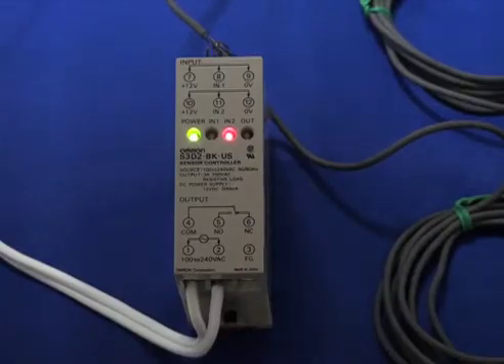Also consider that this same sensor controller can be used for the opposite application when you're trying to determine when you're running out of a product, like in a consumption type application. For instance, a gluing machine or a printing machine where you're trying to keep track of the consumption of ink or glue. In that case, you reverse your sensors, you change a dip switch, and then you have the reverse logic where as your tank becomes empty, your low level sensor tells a pump to turn on and it pumps ink into your vessel and stops when it hits a high level.